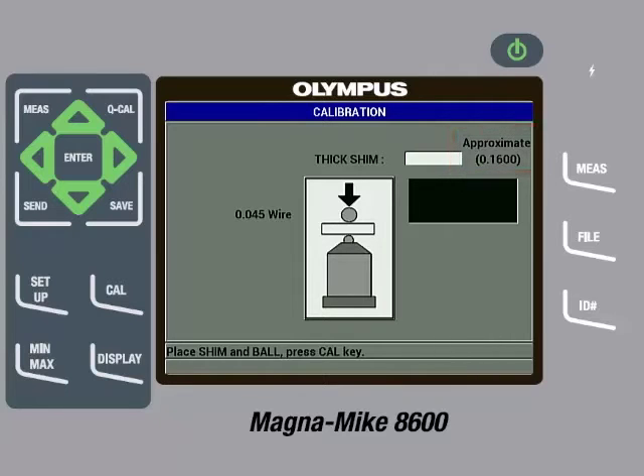The next step is to take out the 86W-CAL-160 reference standard. The top cap can then be unscrewed enough to allow for the wire to be slid through the slot on the side of the fixture. Once again, make sure that the wire is on top of the shim so that when it is placed on the probe, the shim is between the wire and the probe tip.